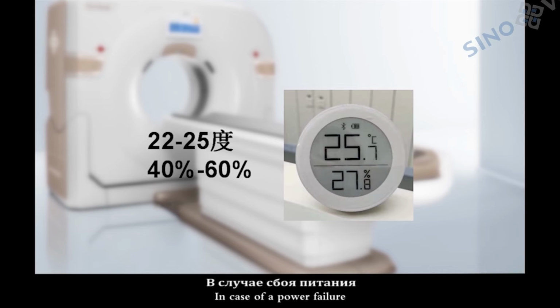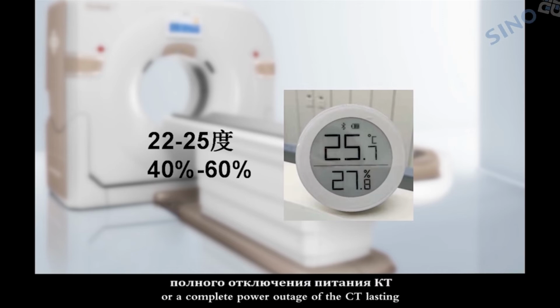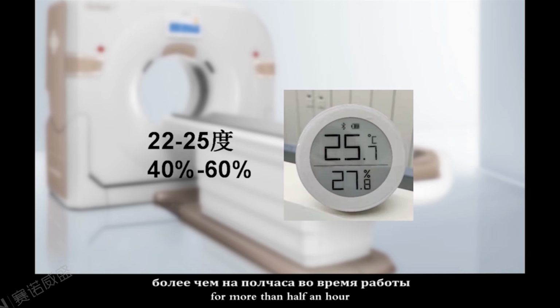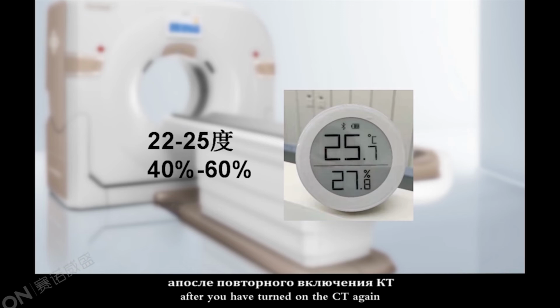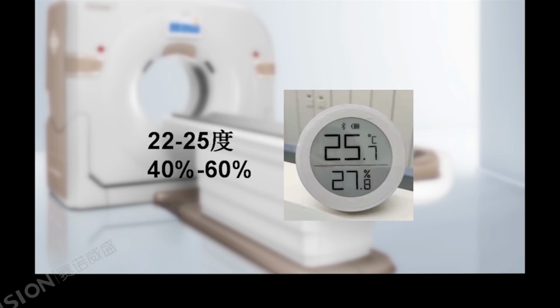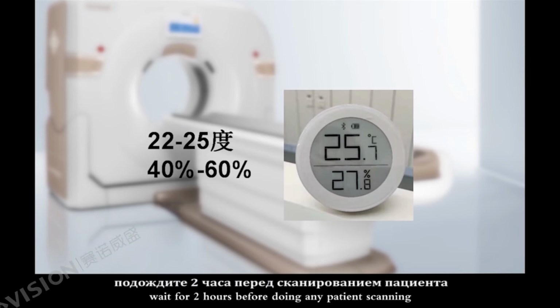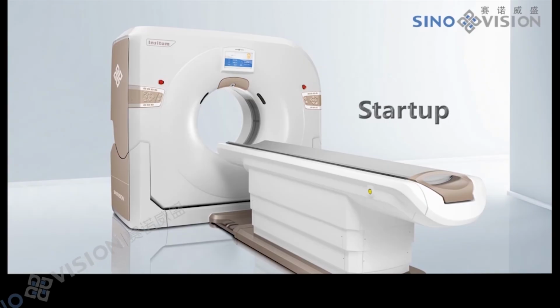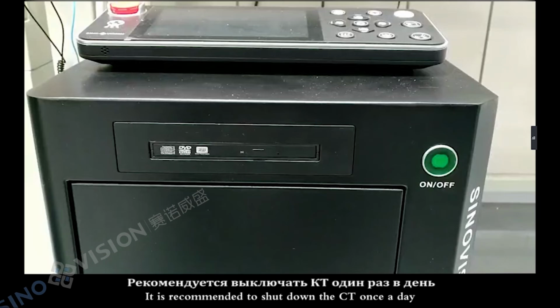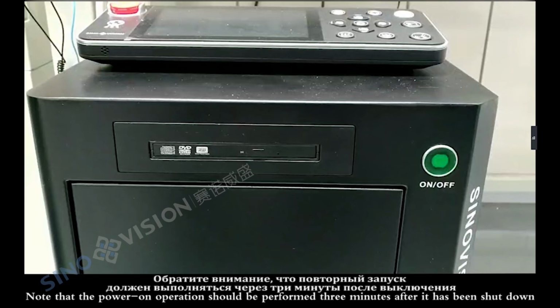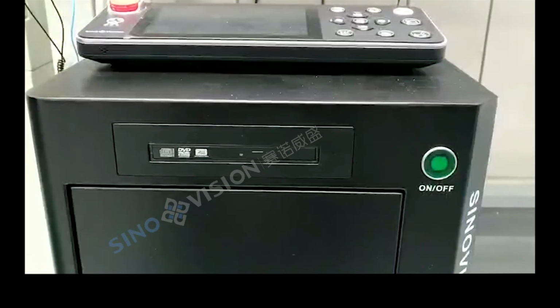In case of a power failure or a complete power outage of the CT lasting for more than half an hour, after you have turned on the CT again, wait for 2 hours before doing any patient scanning. It is recommended to shut down the CT once a day. Note that the power on operation should be performed 3 minutes after it has been shut down.